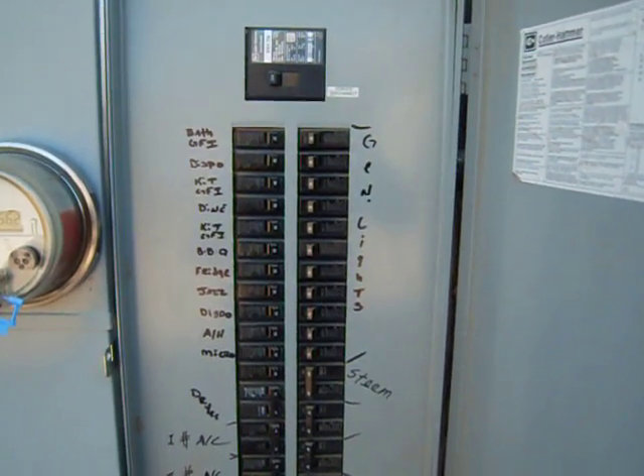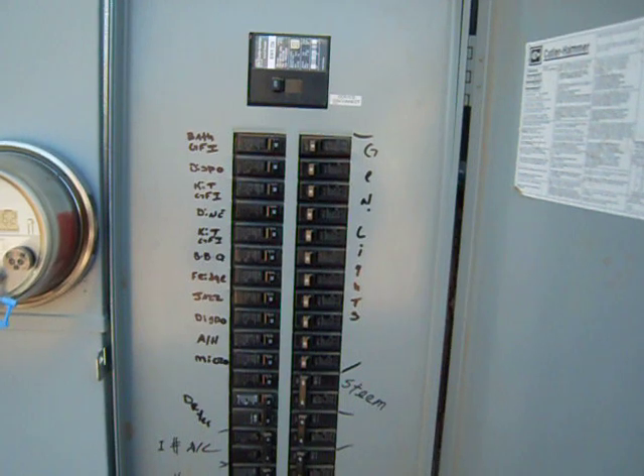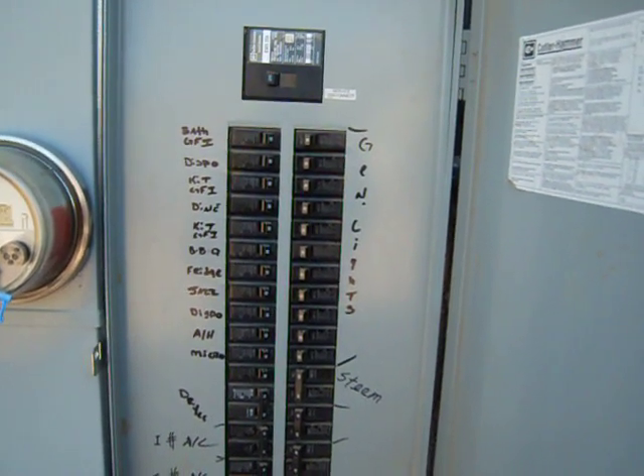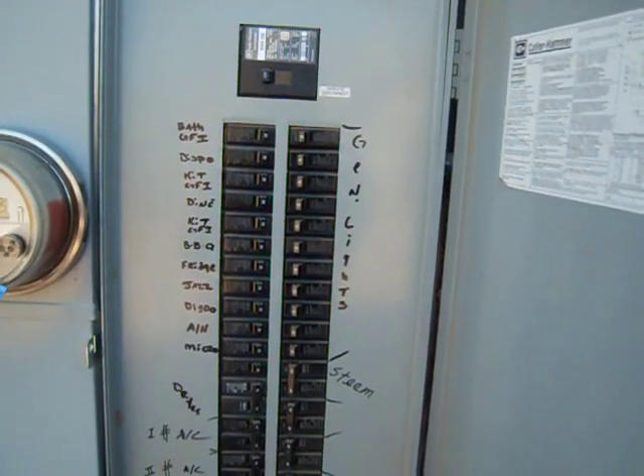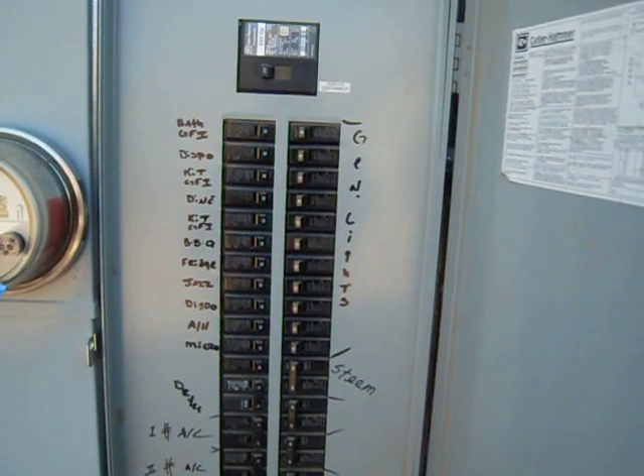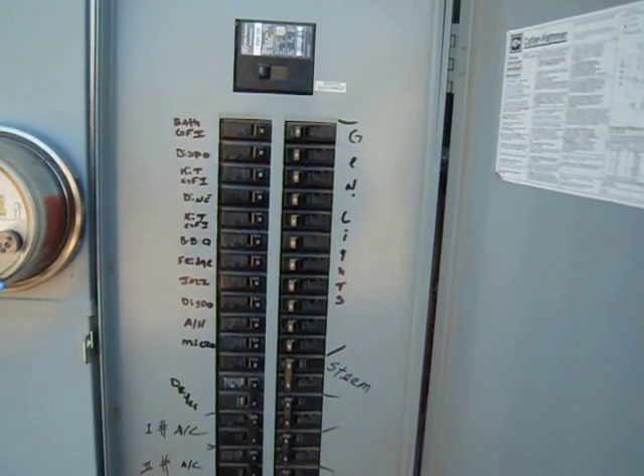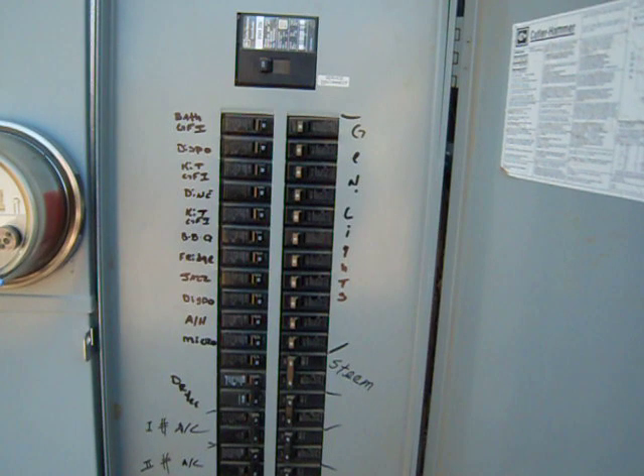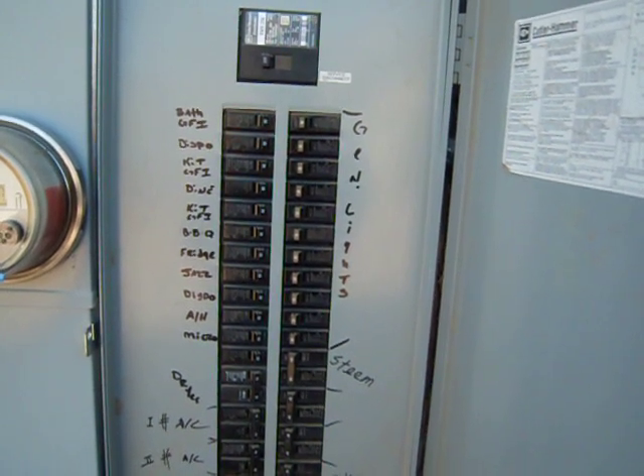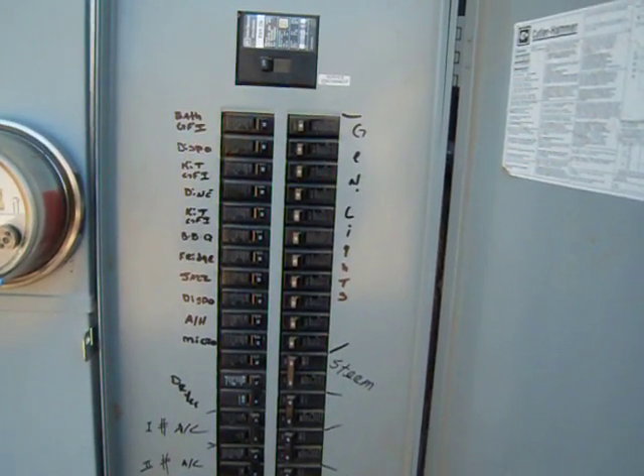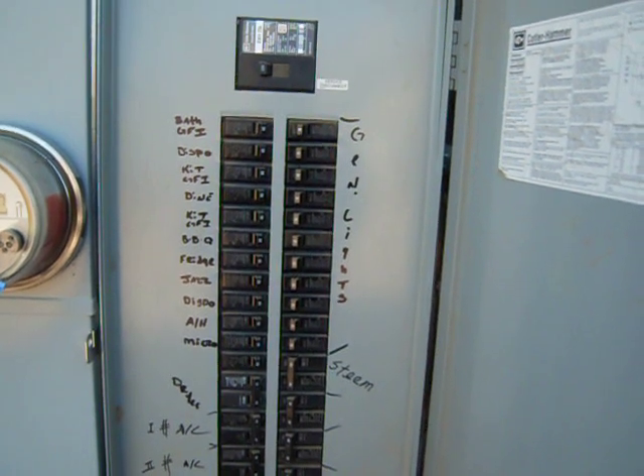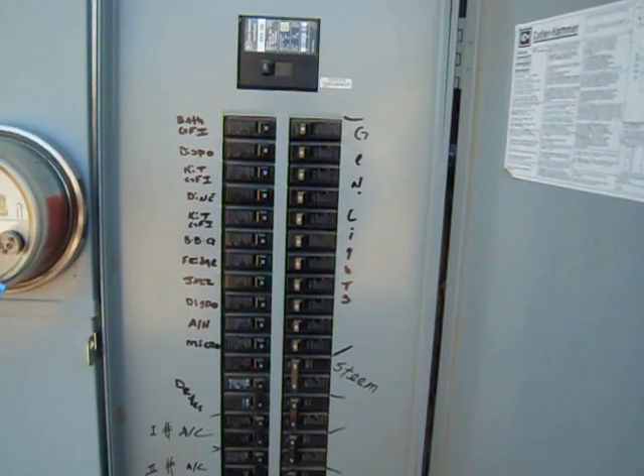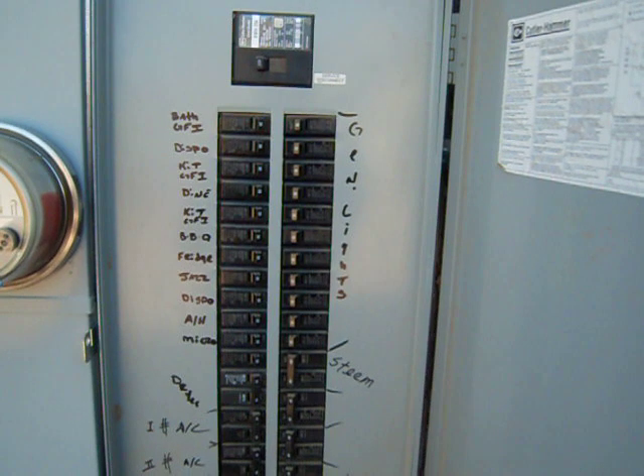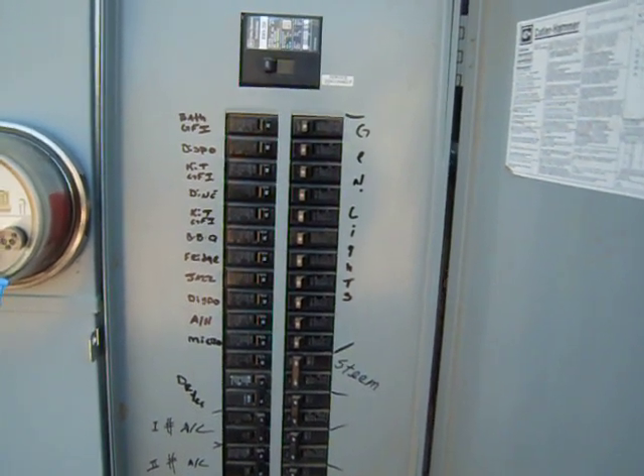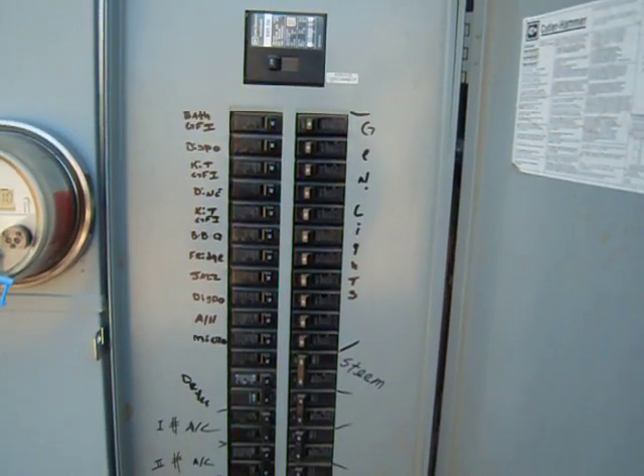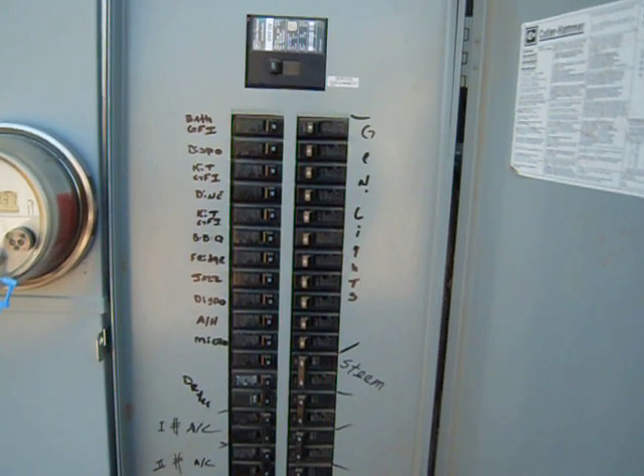On your single pole breakers, you're going to have two different sizes in there most likely. You're going to have 15 amp and 20. The 15 amp breakers are for generally your lighting and most receptacles in your house. Receptacles you'd find in your bedrooms and hallways. And then your 20 amp breakers are for your larger loads. They're things like your kitchen appliances, your disposal, dishwasher, your refrigerator, freezers. You'll find microwaves on there and an assortment of other things.